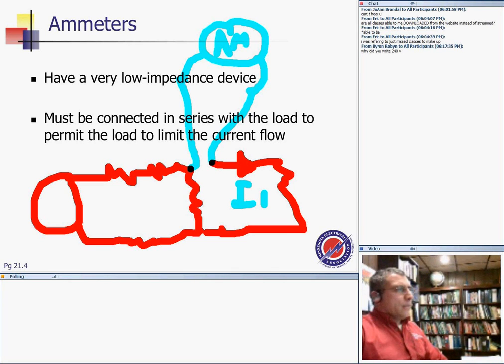Now, I'll tell my friend Eric that you would never open a 4,000 amp switch gear this way. This method is for DC, small amps, up to 10 amps, guys. But for AC 4,000 amp switch gear, we use the principle of the clamp-on ammeter. That's induction. We'll come to induction in a second, but this is a really interesting concept.